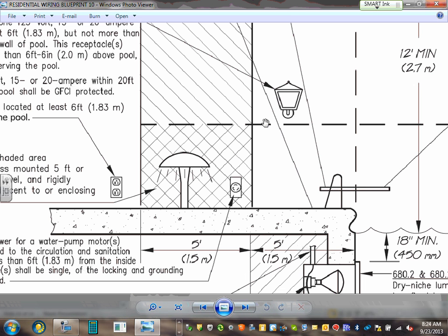Okay, so for storable pools, spas and hot tubs, you have to have at least one receptacle, exactly the same rule as for the swimming pool. Not closer than 6 feet, and it has to be GFCI, one receptacle, 120 volt, 15 or 20 amp. The receptacle must be located at least 6 feet from the hot tub. For a 120 receptacle, 30 amp or less, anything located within 10 feet of the spa or hot tub, up to 30 amps, has to be GFCI'd.